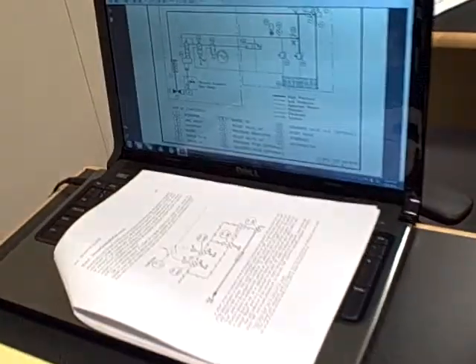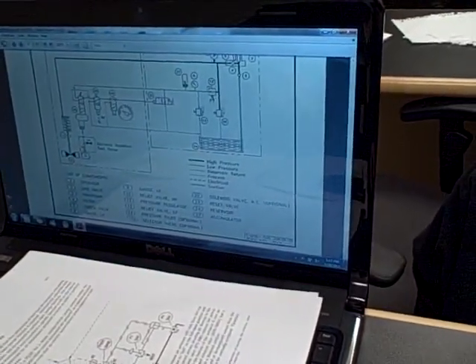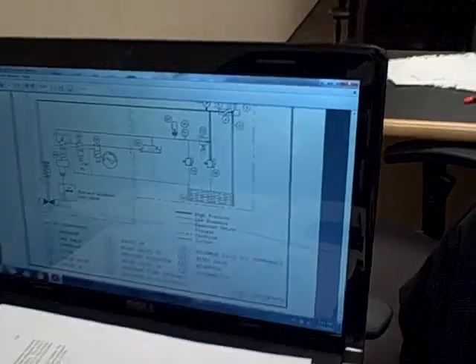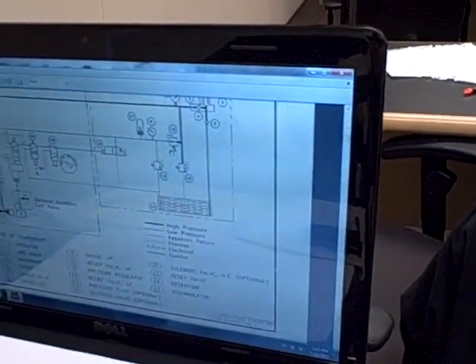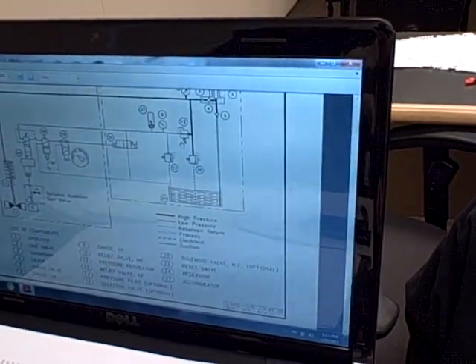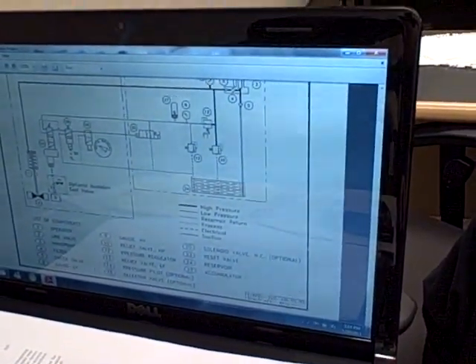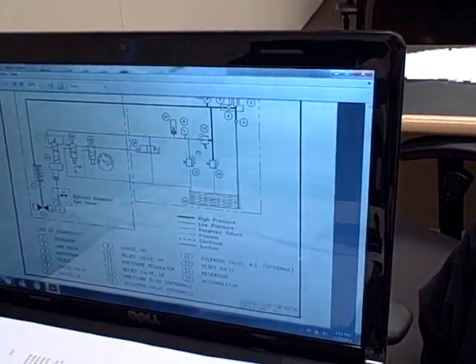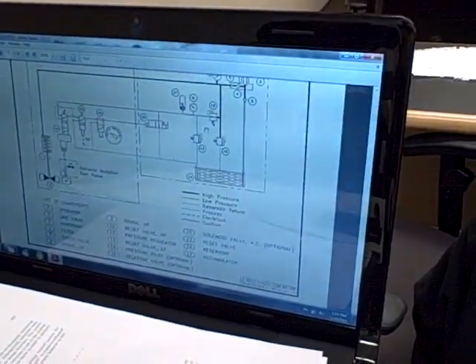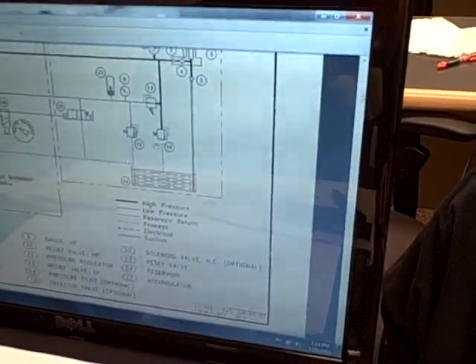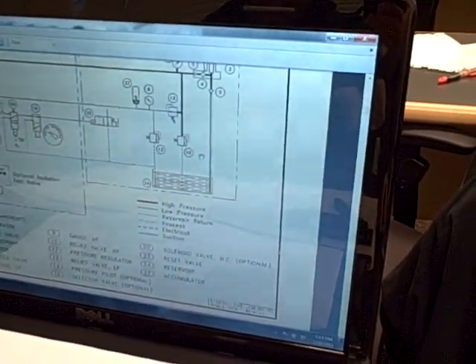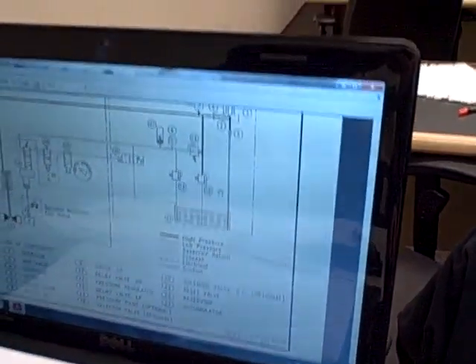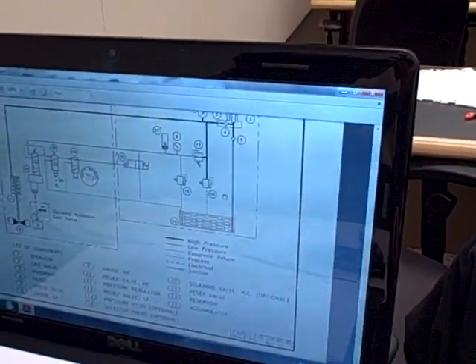So this number 12 right here — it's being held down by pressure. That little dash line on the side of number 12 is pushing that arrow sideways. When there is no pressure, the arrow lines up. As pressure builds up, the valve starts to shut off, so it's regulating pressure downstream by shutting off additional oil when the pressure gets too high. Now that other valve, number 10, just down from there is a different style — it begins to open up as it senses more upstream pressure, which prevents you from generating too much pressure. But regulator number 12 only passes the right amount of oil to get the pressure downstream.